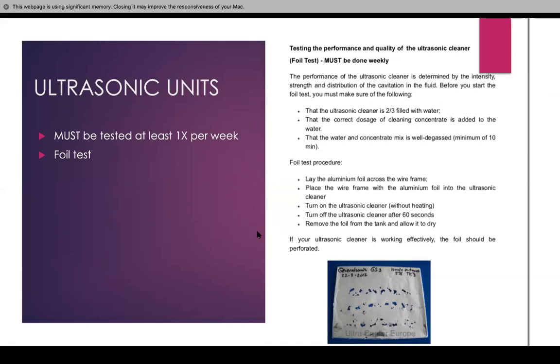For the foil testing procedure, you lay aluminum foil across the wire frame. Place the wire frame with the aluminum foil in the ultrasonic cleaner, turn on the ultrasonic cleaner without heating, and then turn it off after 60 seconds. Remove the foil and check for perforations — tiny holes in the foil. We also label when it's done for record keeping. If you find these perforations, that means your ultrasonic is effectively working. There is also a pencil mark test, but this foil test is the best way to do it.